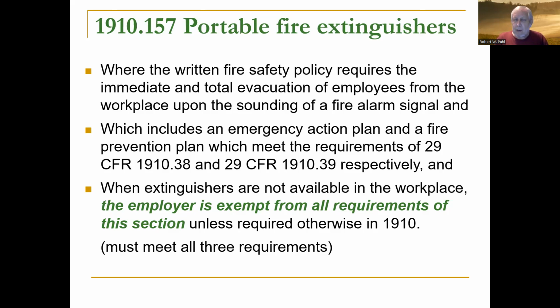All right. And you have an emergency action plan and a fire prevention plan, and extinguishers are not available in the workplace. So do you have to have extinguishers in the workplace? No, if you do all of this. Now, your insurance company may have a little different idea about that, but in my opinion, it's a good idea to have fire extinguishers in the workplace and to have people trained on them. And you can designate in your plan that the supervisors are going to do it. Then you've got to train them.